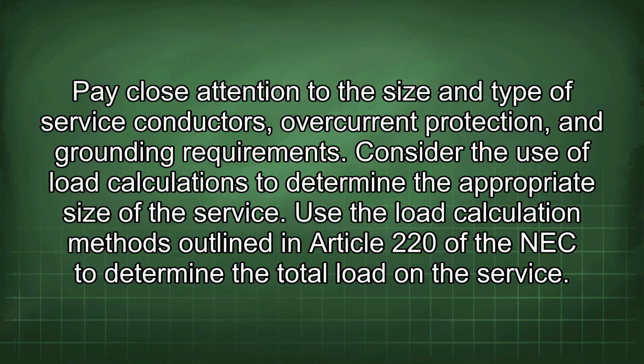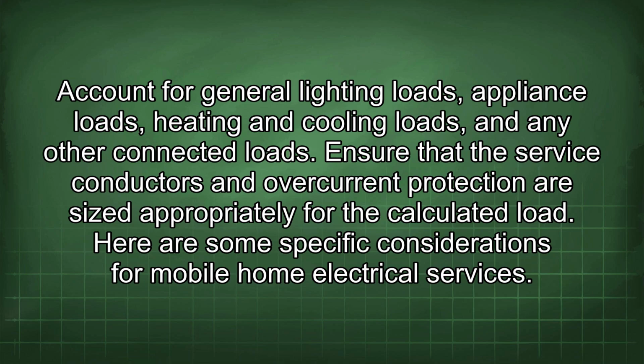Consider the use of load calculations to determine the appropriate size of the service. Use the load calculation methods outlined in Article 220 of the NEC to determine the total load on the service. Account for general lighting loads, appliance loads, heating and cooling loads, and any other connected loads. Ensure that the service conductors and overcurrent protection are sized appropriately for the calculated load.